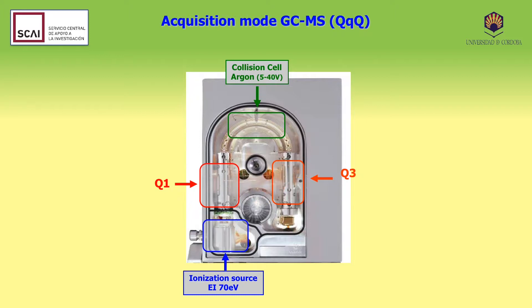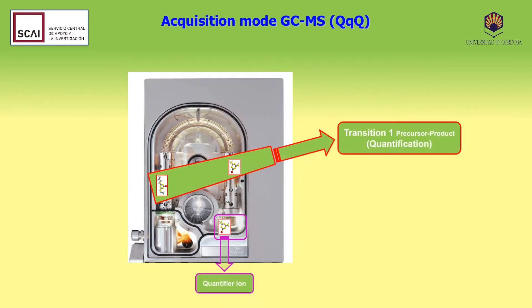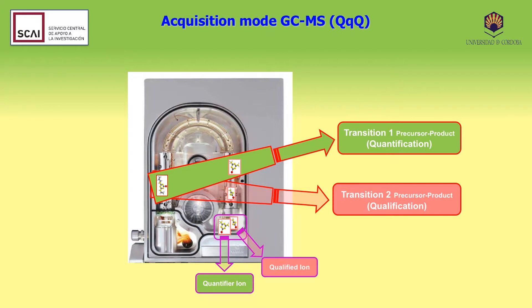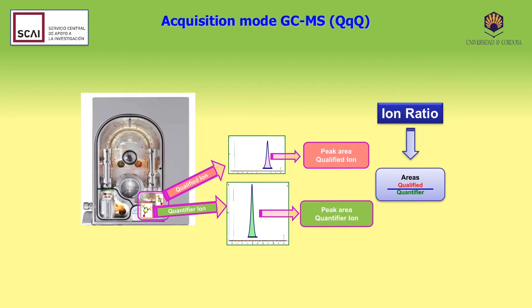Ions are formed at the ionisation source by electronic impact. In the first quadrupole, the precursor ion is filtered, and then broken up into fragments induced by energy generated by ionised argon. In the third quadrupole, or Q3, product ions are filtered and then quantified in the detector. Transition one will produce the quantifying ion, while transition two will produce the qualifying ion. The division between the areas of both peaks is the so-called ion ratio parameter.